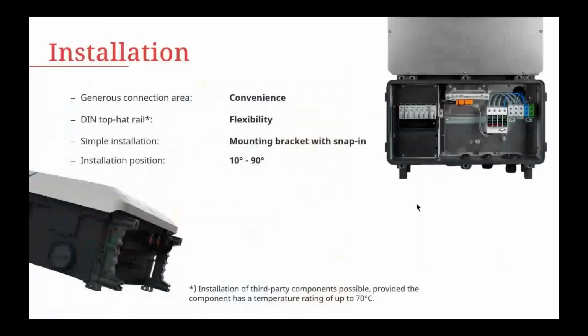So for optimal use, you can see that the inverter design is very easy on the eye and very user friendly for installation and for EPC companies as well, with a very convenient way of installing the SPDs and AC SPDs inside the inverter. We also have an extra DIN rail inside the inverter where you can put any third-party component or device, such as generator controllers. There is a lot of space inside the inverter cabinet where you can install the zero export device or any external device that you want in the IP65 compartment of the inverter, without any external DB box requirement.